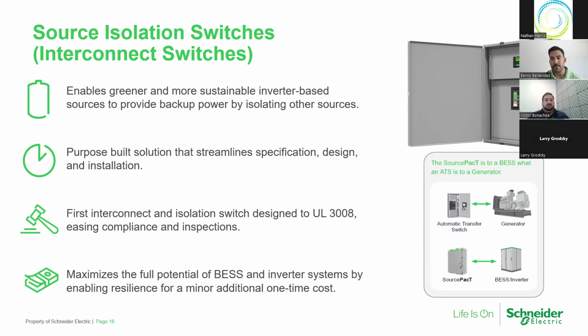Whereas some other solutions provide an overspecified product where you're electrically modifying each breaker, adding a PLC, really adding costs and more simple transactional business. If you're looking to create isolation to enable that battery resiliency, the source isolation switch is one approach to achieve that. And we'll use the analogy: what an ATS is to a generator, SourcePacT is to a battery storage system / inverter system. And that's the way you can probably look at it in order to connect the dots.